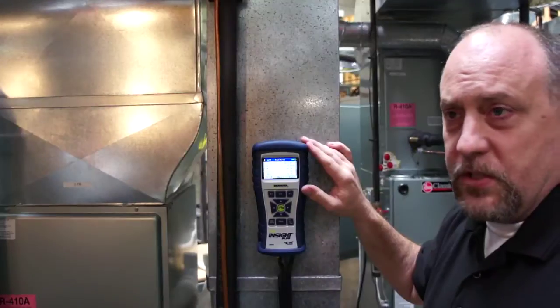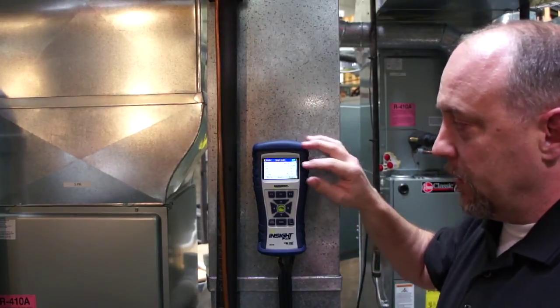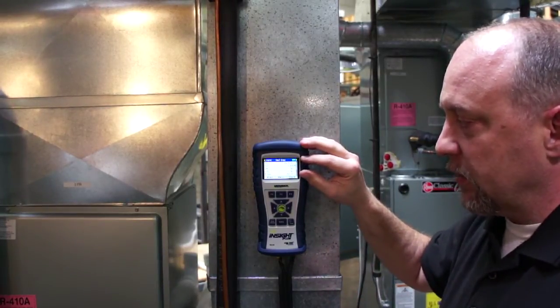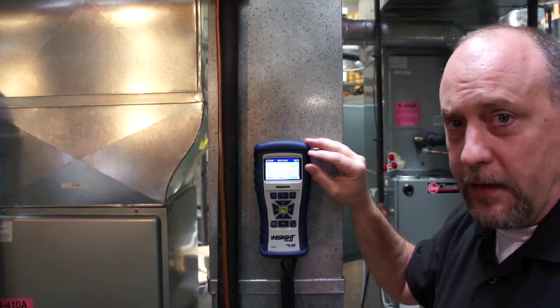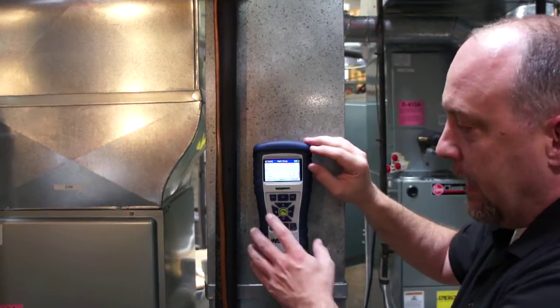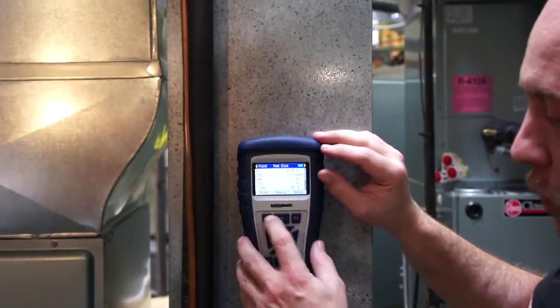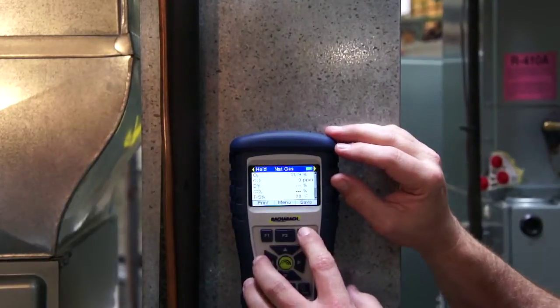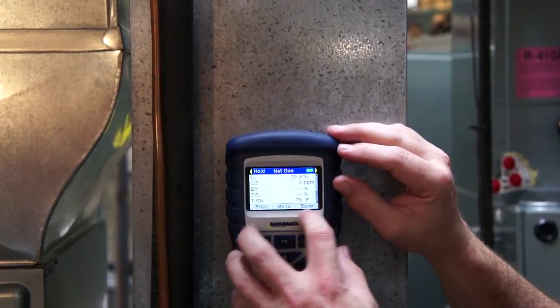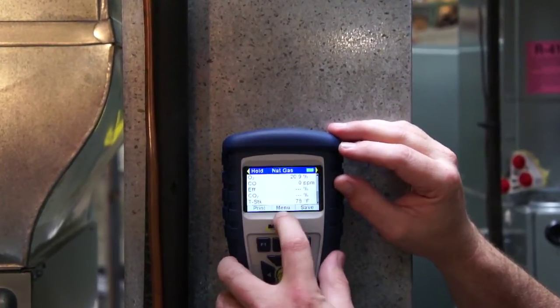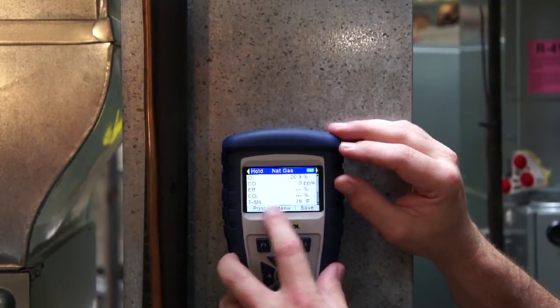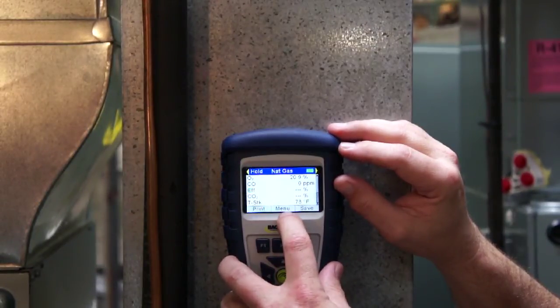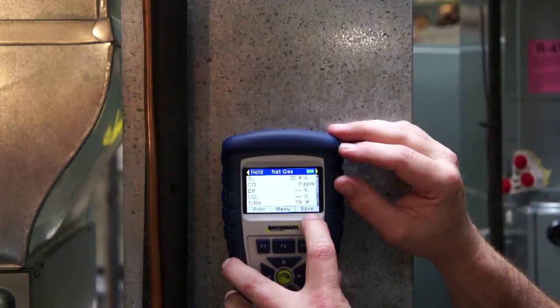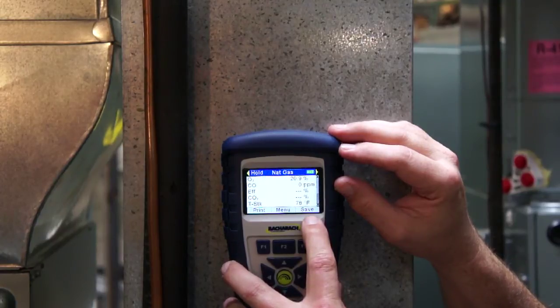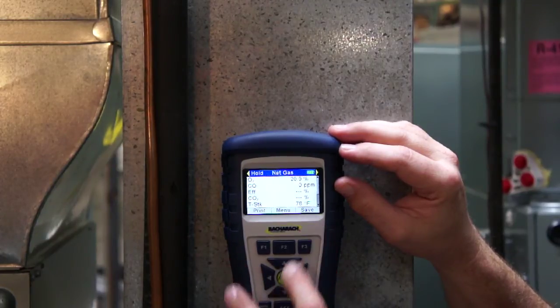All right, so once the instrument comes up, you're going to get it into the measurement screen here, and I thought I'd just take a second and go over how the instrument's actually configured. And really what you've got here is F1, F2, and F3 are actually soft keys now. And they're basically driven off these menus right here. So we got the print, the menu, and the save button right here, where we can either print that information, go into our configuration menus, or we can save that information to one of the storage spots in the instrument.